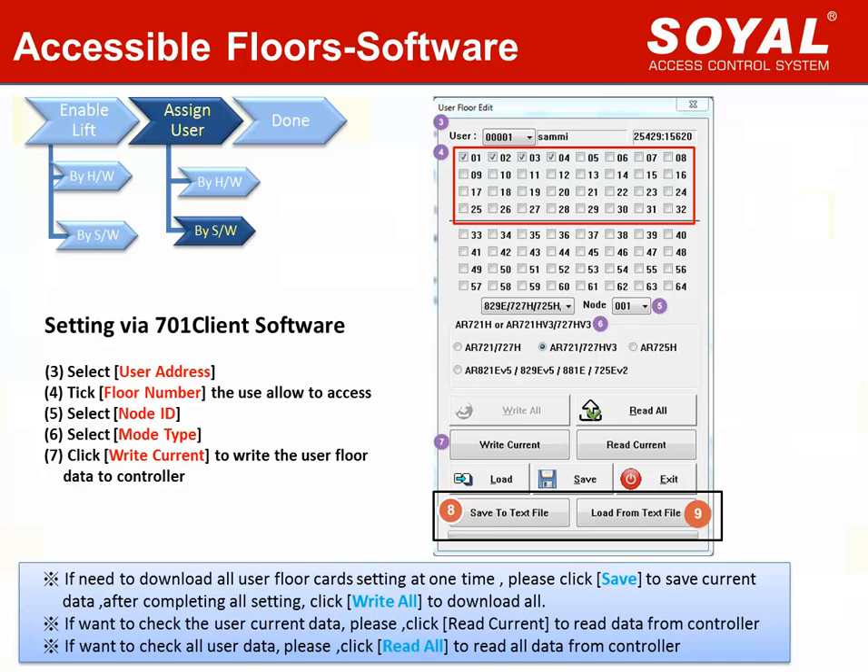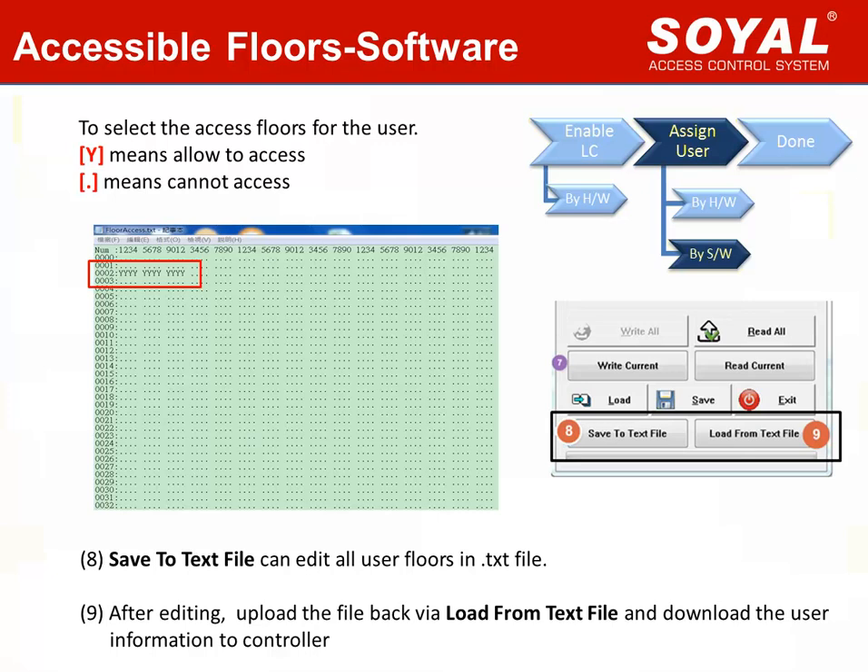The user floor setting can be downloaded to the connected controller. There are three notes for your attention. If you need to download all user floor card setting at one time, click Save to save current data. After completing all settings, click Write All to download all to controller. If you want to check the user's current data, click Read Current to read data from controller. If you want to check all user data, click Read All to read all data from controller. Another simple and fast way is to edit user floors in a text file. Select the access floor for each user card — Y means allowed to access, dot means cannot access. After completing the user floor setting, upload the file using the Load from Text File option and download the user information to the controller.